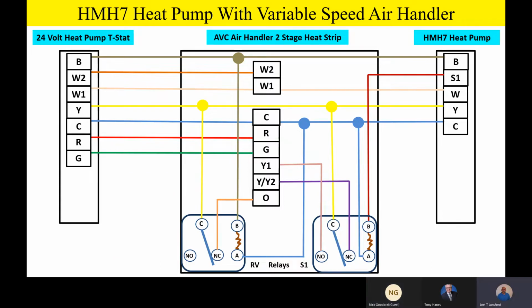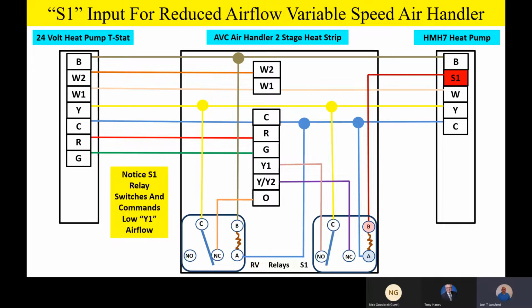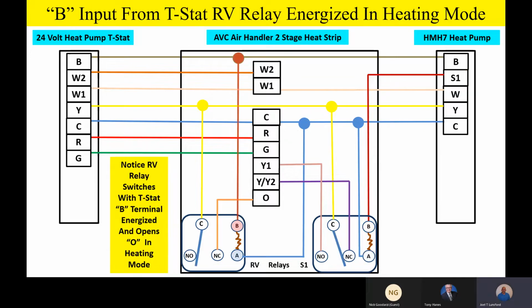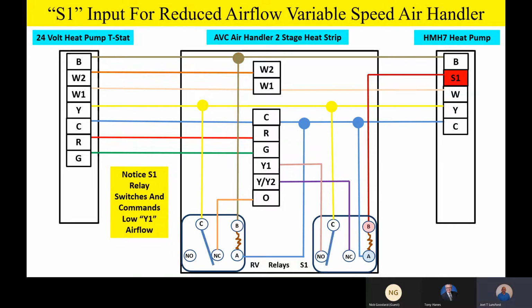All right, so as we start taking a look at some advanced functions on this thing, let me do that animation one more time. If we're calling for reduced airflow outside, we're going to generate that S1 signal outside. It's going to switch the S1 relay, and we're going to command low speed or low airflow on Y1. Now, if we go into the heating mode of operation, watch this. Let me back up. If we go into the heating mode of operation, we're going to energize the B terminal on the heat pump for heating mode of operation, but we're also going to energize the coil of the RV relay. Watch this. Bang, right there.